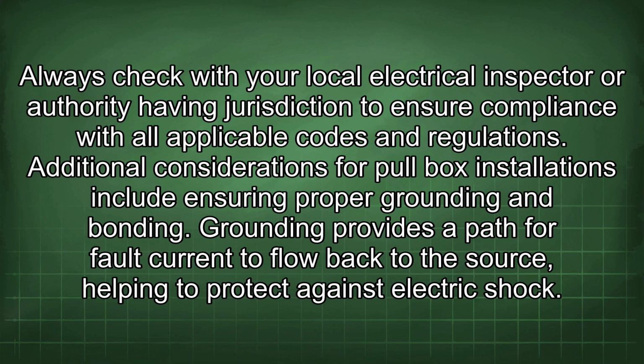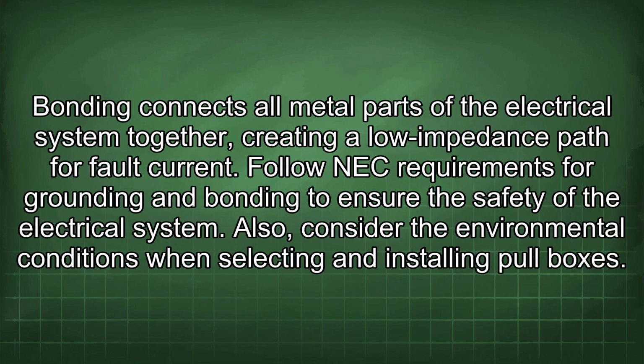Additional considerations for pull box installations include ensuring proper grounding and bonding. Grounding provides a path for fault current to flow back to the source, helping to protect against electric shock. Bonding connects all metal parts of the electrical system together, creating a low impedance path for fault current. Follow NEC requirements for grounding and bonding to ensure the safety of the electrical system.